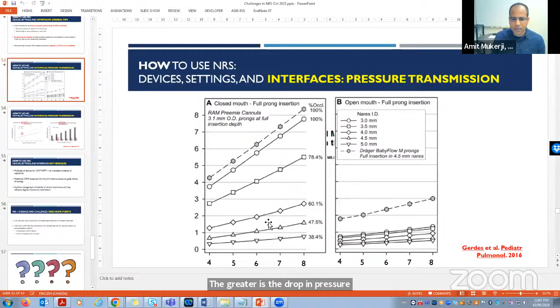The other factor is the degree to which the RAM cannula occludes the nares. As you go across these, the smaller the RAM cannula gets, the less occlusion there is, and the greater the drop in pressure. So that's a very important thing to keep in mind: if you take the same settings from a traditional interface on CPAP or NIPPV and apply them to the RAM cannula, the pressure transmitted to the airways will be significantly lower, even if the ventilator is reading that the pressures are adequate.